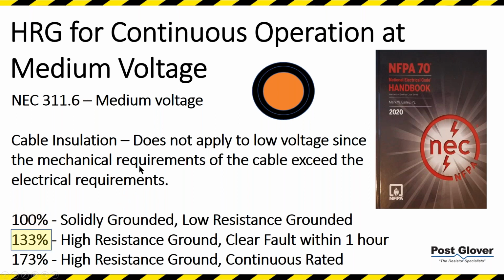133% per the standard, you're going to be using a high resistance ground system that has to clear within the hour. There are people who do this at medium voltage for sure, I've heard. It's a lot more energy at medium voltage. There's a lot more potential for issues depending on what kind of equipment you have. So it's a safe way to go for some people. And then 173% for the continuous rated cable on your ground fault.